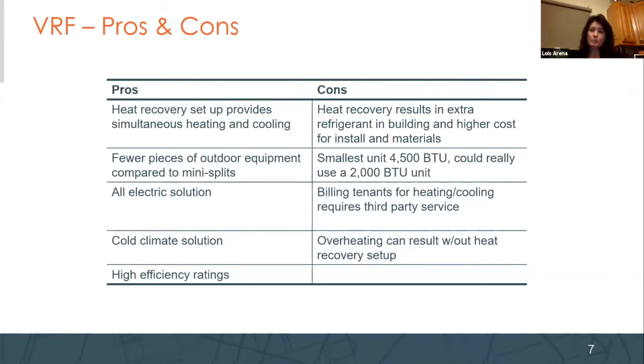If you're trying to bill your tenants for heating or cooling or both, you actually have to have a third-party person process that information so that you can parse it out by apartment, because you've got one condenser handling 10, 15, 20 apartments, right? So you need somebody to handle that billing for you. And then if you do not have heat recovery, overheating is a common result of a heat pump system. And I'm going to get into that a little bit more.